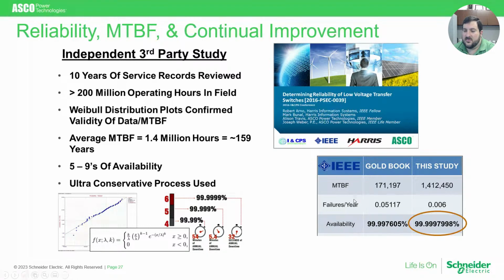So again, if you look over here, it's 1.4 million hours of operation, meaning that the expected failure rate is 0.006 failures per year if you look at the total install base relative to the number of failures reported. And then that results in the 99.999 availability, because you look at the number of hours that the equipment's been running, how long it was running before those failures were experienced, and that's how you get to this number at a high level. So extremely high levels of reliability, mathematically proven based on products that are actually in the field and in operation with customers today, and real-world data, not theoretical or experimental data.